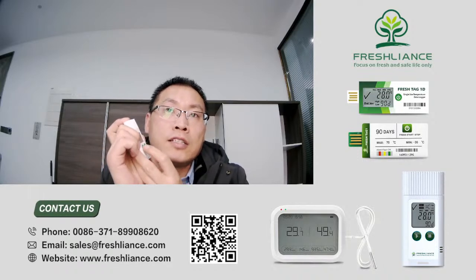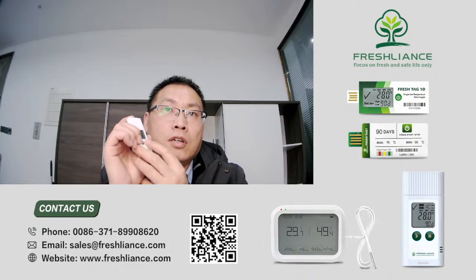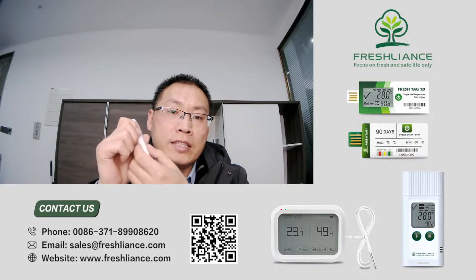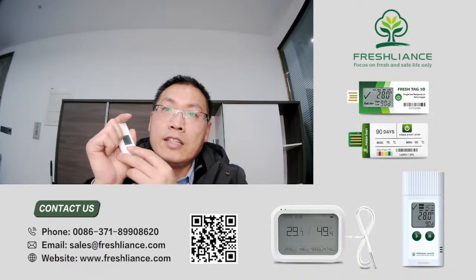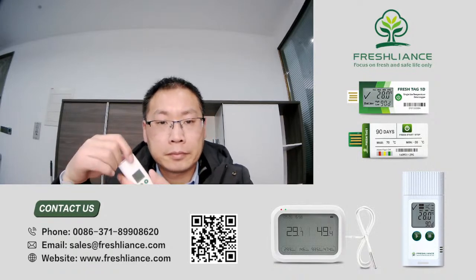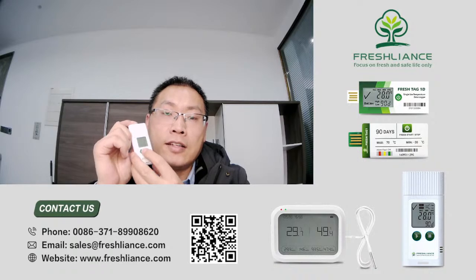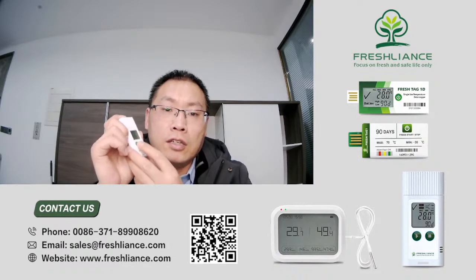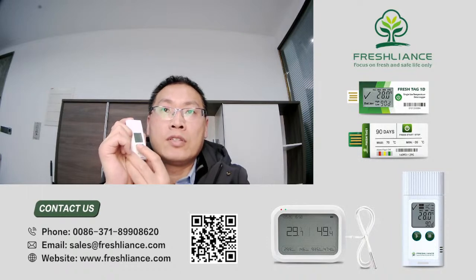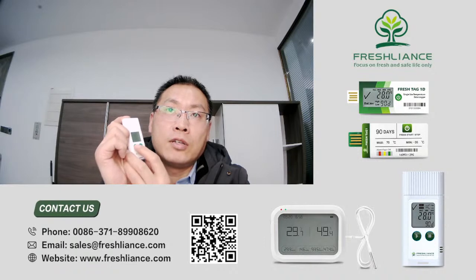During the recordings, sometimes you may need to make a mark on the report, for some reason. Just press the left button for 3 seconds. Then you can make a mark on the report. And for the Tech Plus temperature and humidity data logger, there are pause and continue functions. Just double click the left button, the logger will pause and stop the recordings. Then double press the left button again, it will continue making the recordings.